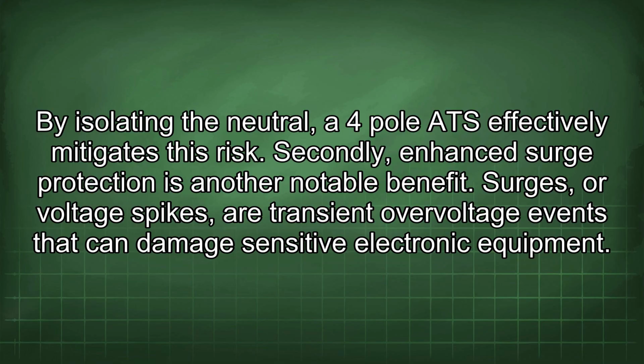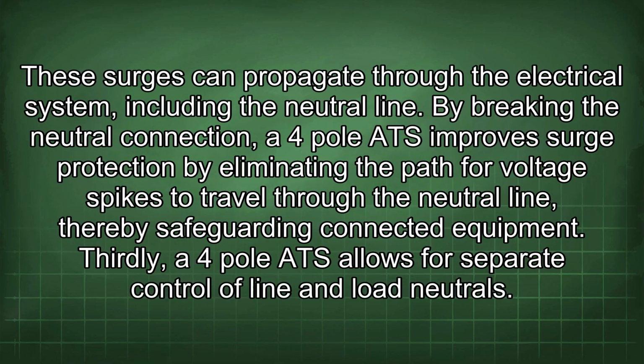Surges, or voltage spikes, are transient overvoltage events that can damage sensitive electronic equipment. These surges can propagate through the electrical system, including the neutral line. By breaking the neutral connection, a 4-pole ATS improves surge protection by eliminating the path for voltage spikes to travel through the neutral line, thereby safeguarding connected equipment.